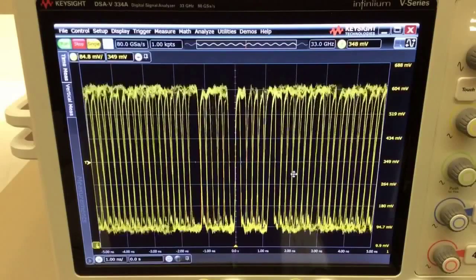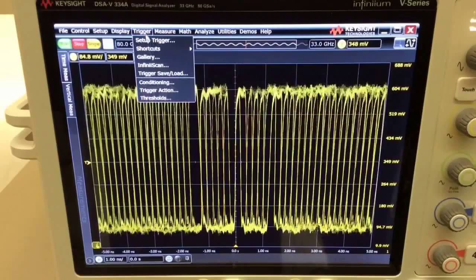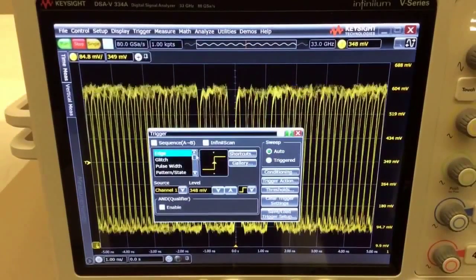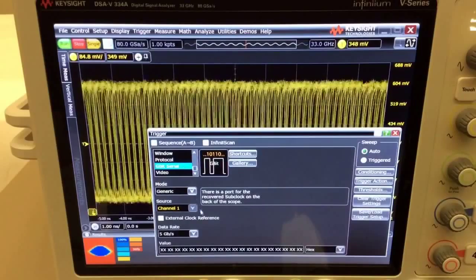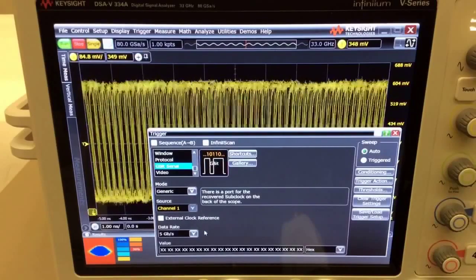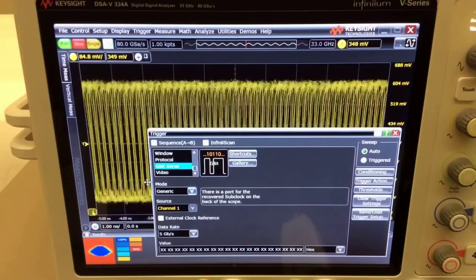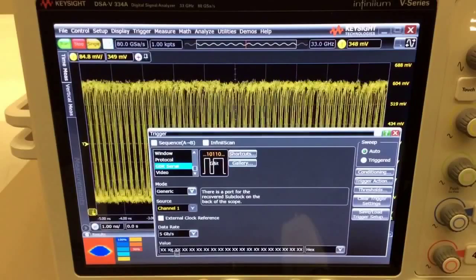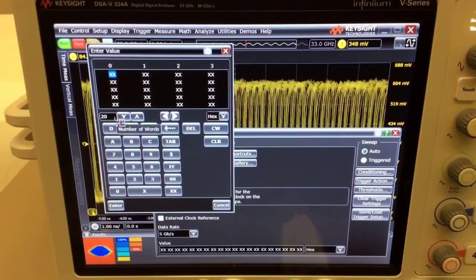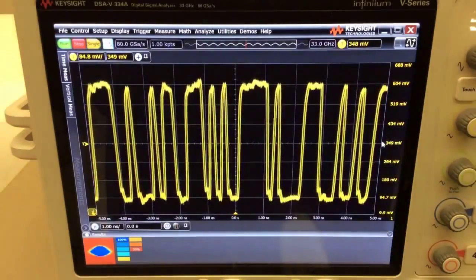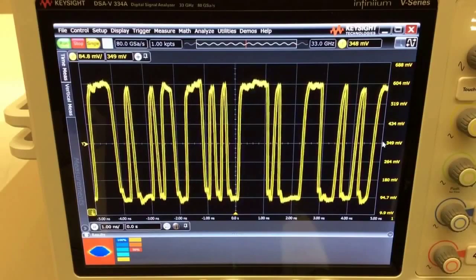In order to access the hardware serial trigger, you first go to the trigger menu in the scope, select Setup Trigger, and scroll down the list until you find the gigabit serial. Select that, and the next step is to configure the data rate. It has already been configured to 5 gigabits per second, which is what the signal is transmitting right now. Next, you want to configure the value, and you can see here it allows me to configure up to 20 words, which is equivalent to 160 bits. I'm just going to show a simple hardware serial trigger here by keying in the F and the A hexadecimal value, and when I hit enter, you can find that the hardware serial trigger is locking into the bit sequence that I want it to trigger on.